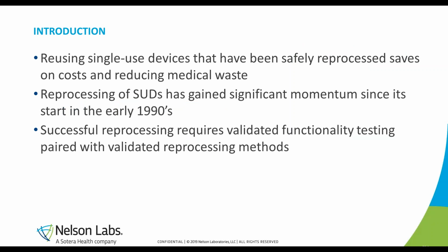As background, the reuse of single-use devices, which have been safely reprocessed by third-party reprocessors, can enable healthcare facilities and providers to maintain a high quality of patient care while saving on costs and reducing medical waste. Reprocessing of single-use devices is not a new concept and has gained significant momentum since the start of reprocessing in the early 90s. Today, many large corporations have a branch or division specifically dedicated to the reprocessing of single-use medical devices. Validated functionality testing, paired with validated cleaning, disinfection, and/or sterilization processes, ensure the safety and compliance with regulatory requirements for the reuse of these devices.